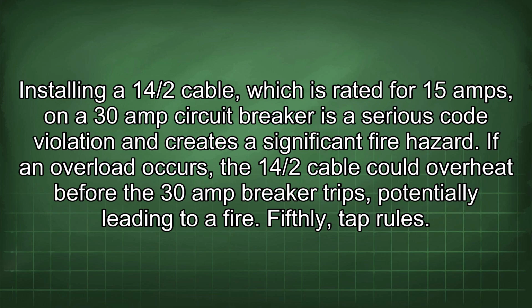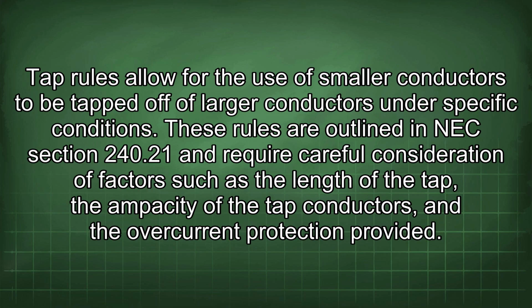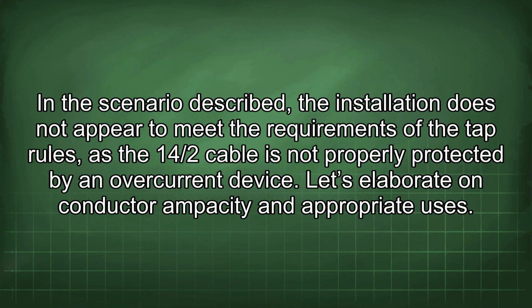Fifthly, tap rules. Tap rules allow for the use of smaller conductors to be tapped off of larger conductors under specific conditions. These rules are outlined in NEC Section 240.21 and require careful consideration of factors such as the length of the tap, the ampacity of the tap conductors, and the overcurrent protection provided. In the scenario described, the installation does not appear to meet the requirements of the tap rules, as the 14/2 cable is not properly protected by an overcurrent device.